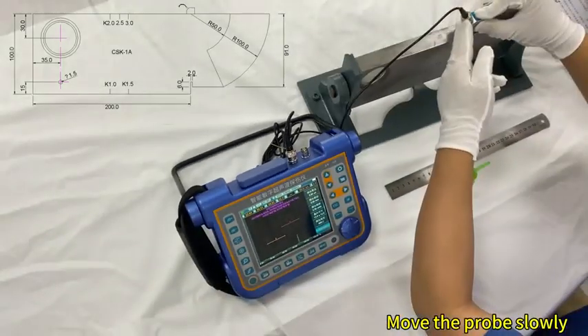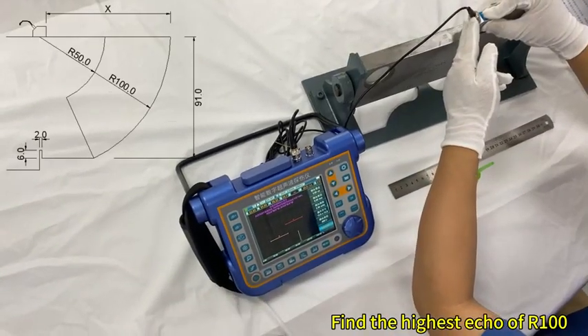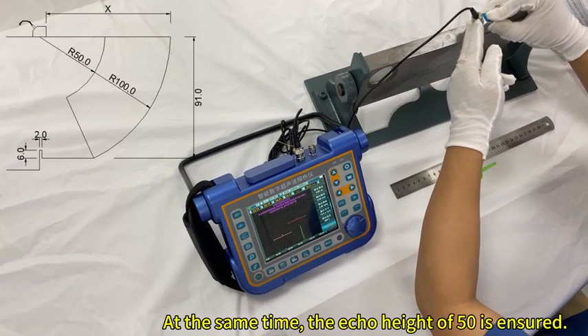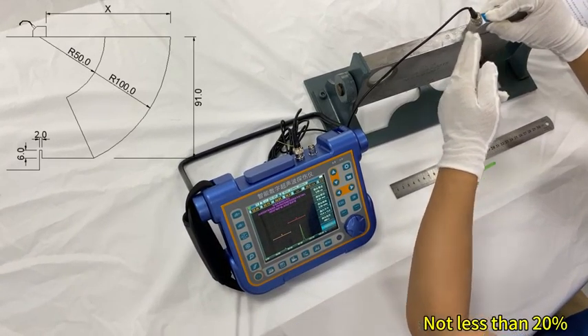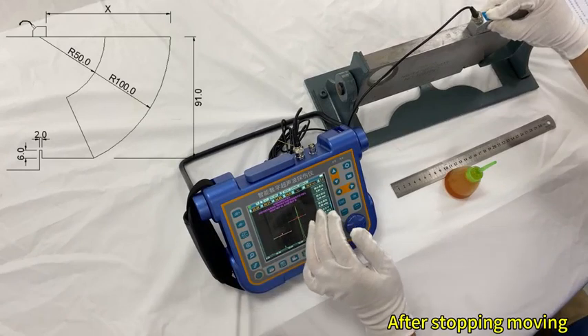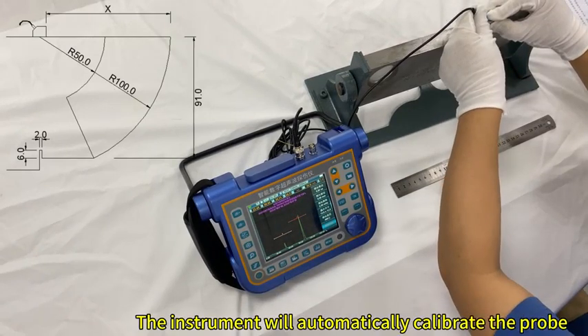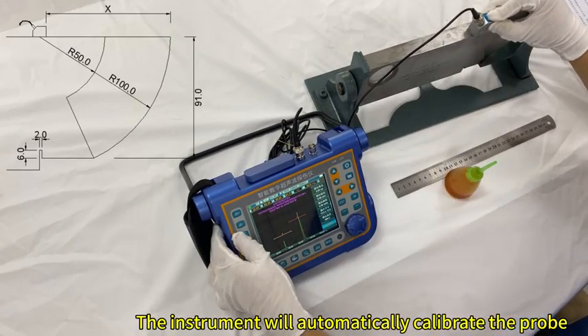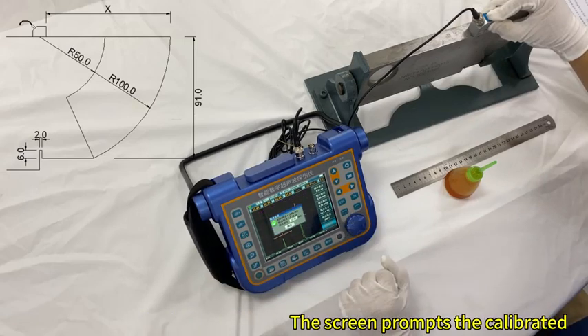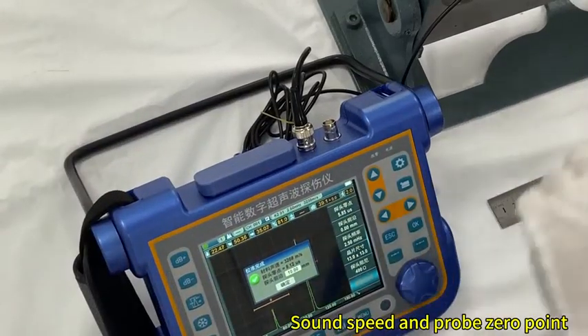Move the probe slowly. Find the highest echo of R100. At the same time, ensure the echo height of R50 is not less than 20%. After stopping moving, press the OK button of the wheel. The instrument will automatically calibrate the probe. The screen prompts the calibrated sound speed and probe 0 point.